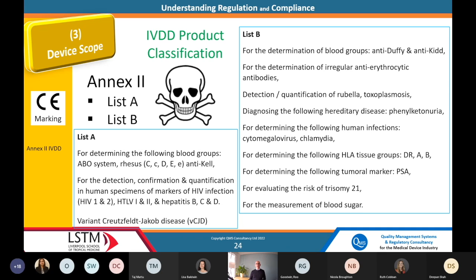And if they don't appear in this list, they get self-declared. And 80% of all diagnostic devices on the market in Europe have been self-declared. Under the regulation, this is going to totally change, and you'll find that 90% of all IVDs will need a notified body before placing them on the market. You can see in the middle above A, specimen receptacles. So that blood tube is captured under Rule 5 and is captured under the IVDR, but it can be self-declared. But pretty much everything else you can think of, anything with a diagnostic capability, is either going to be a B, a C, or a D, D being the highest risk.